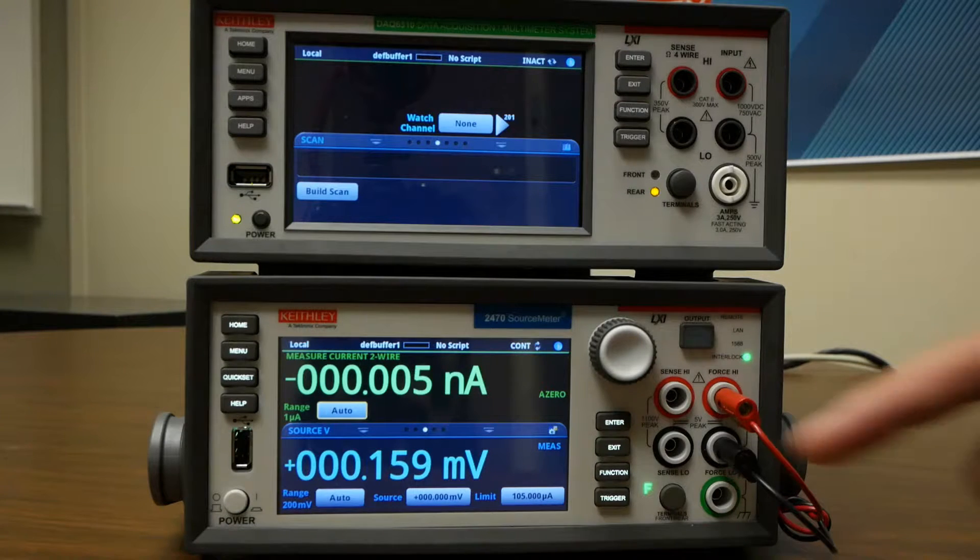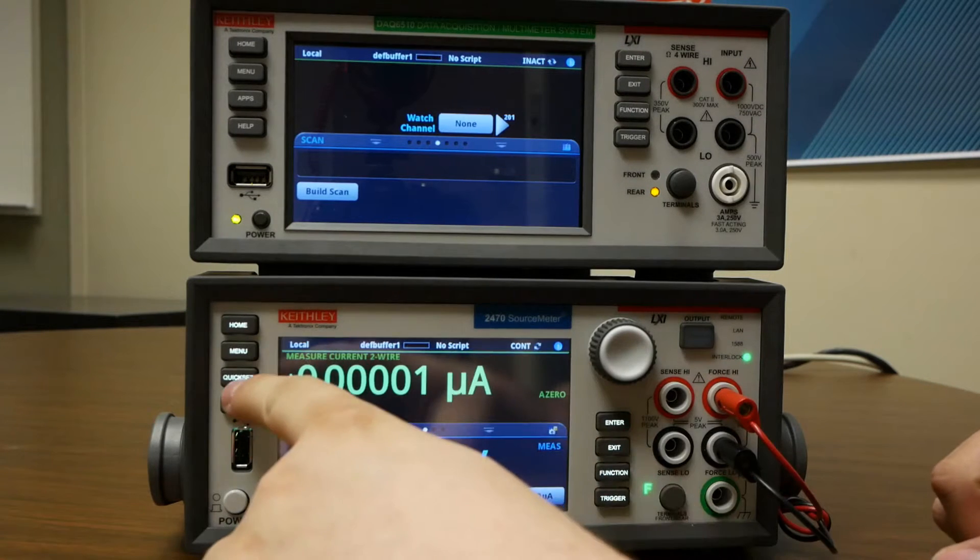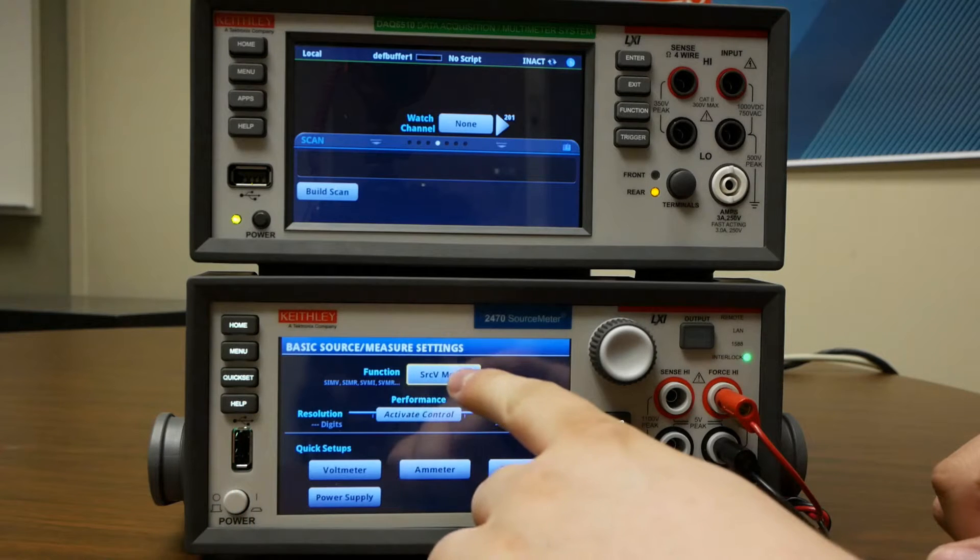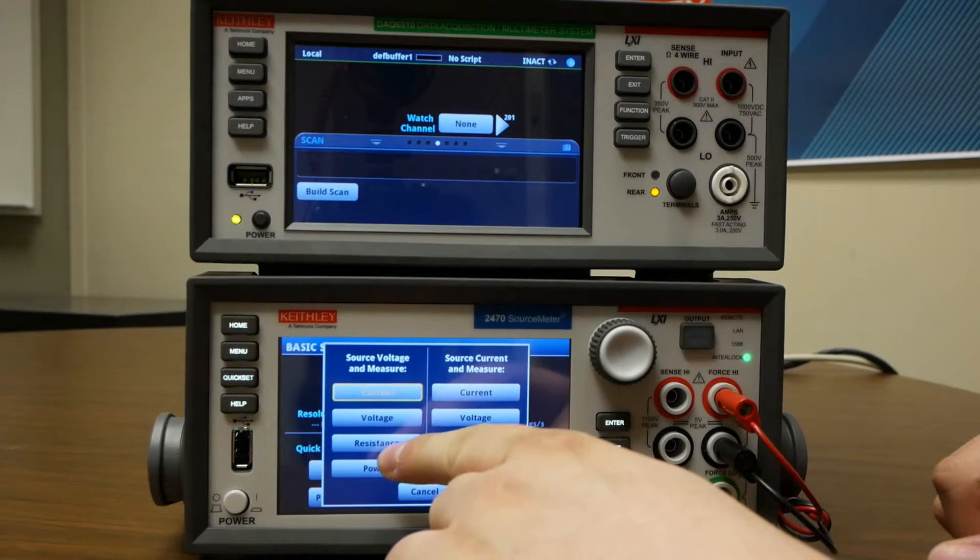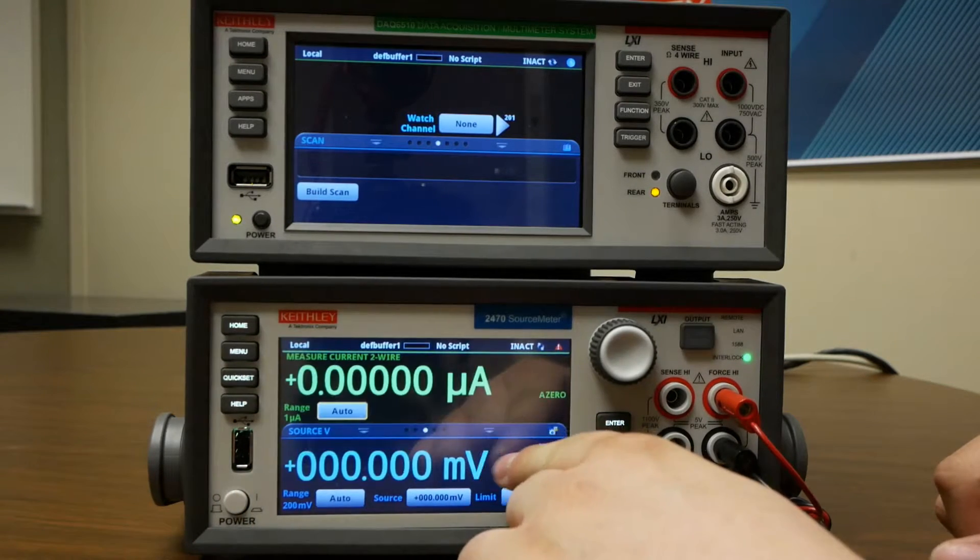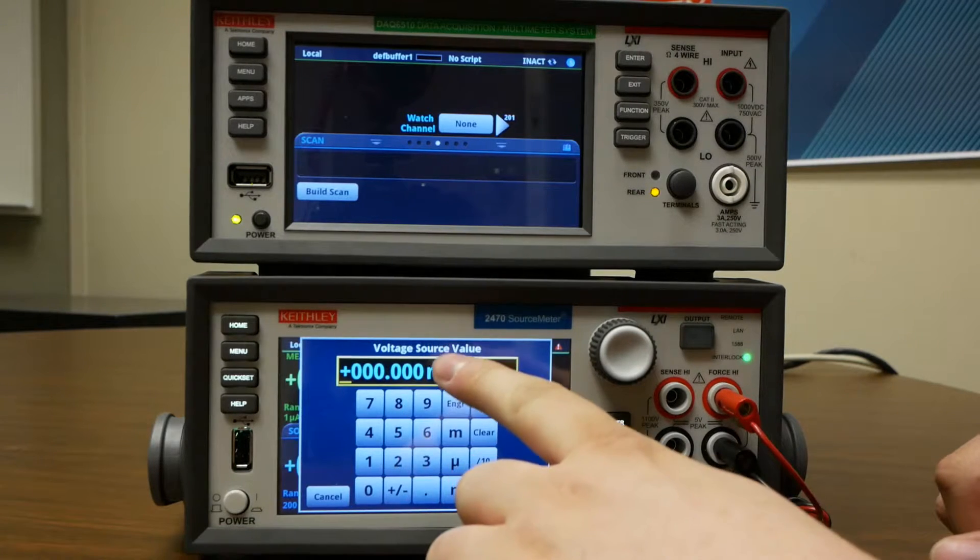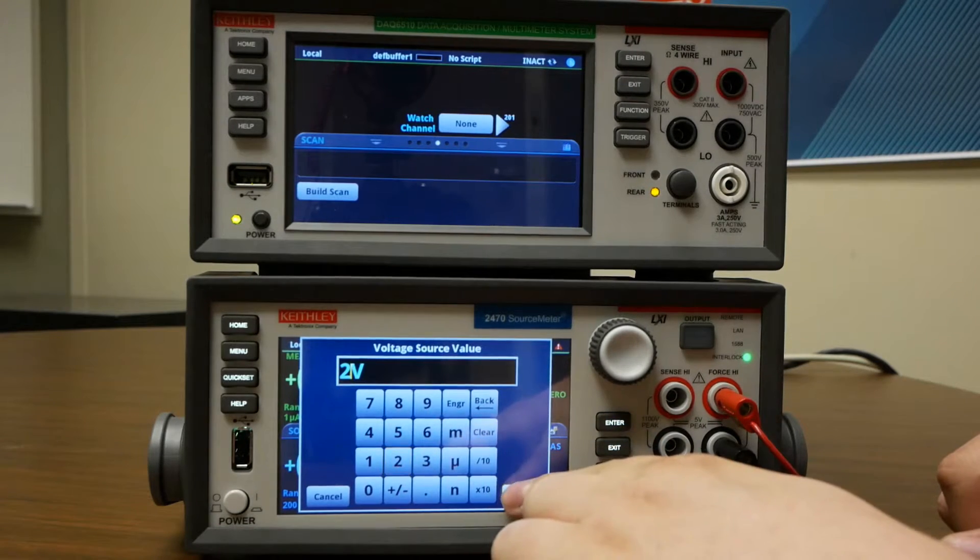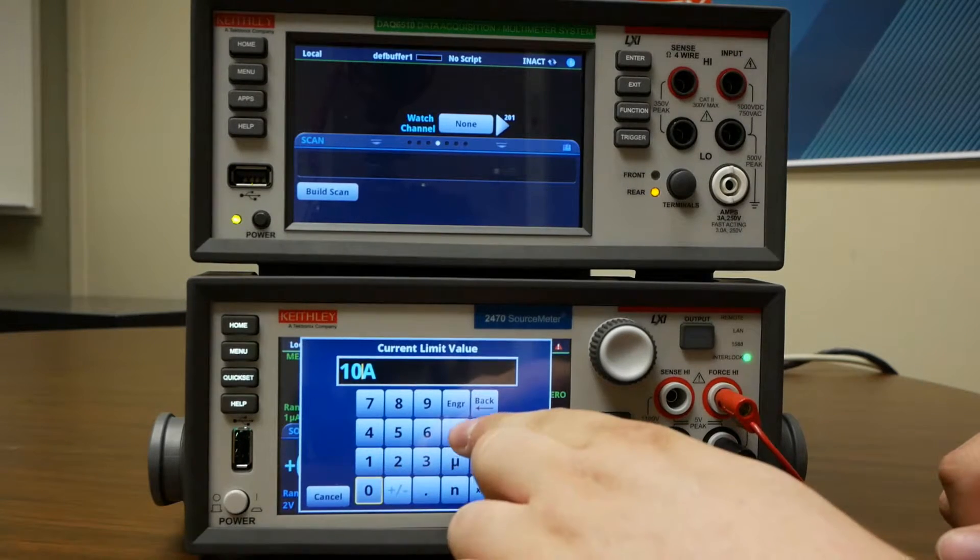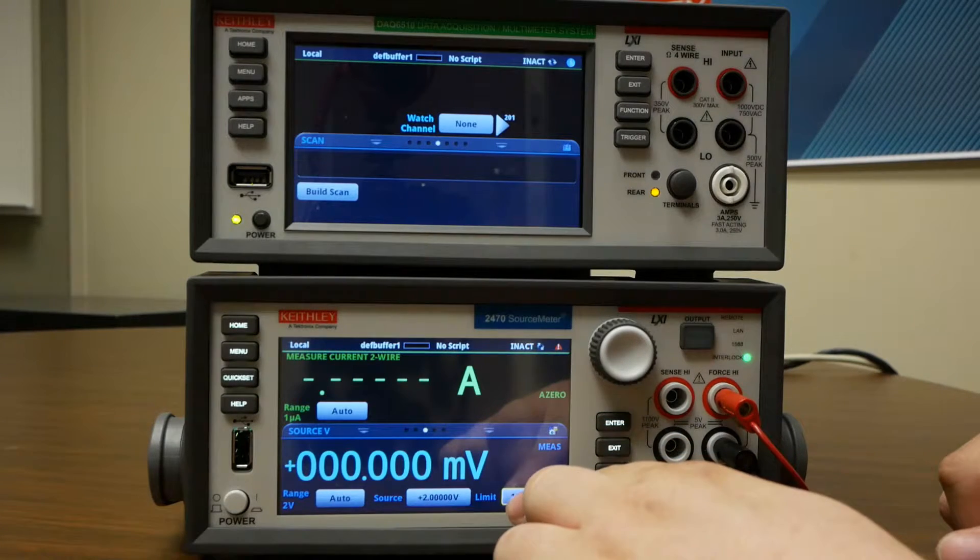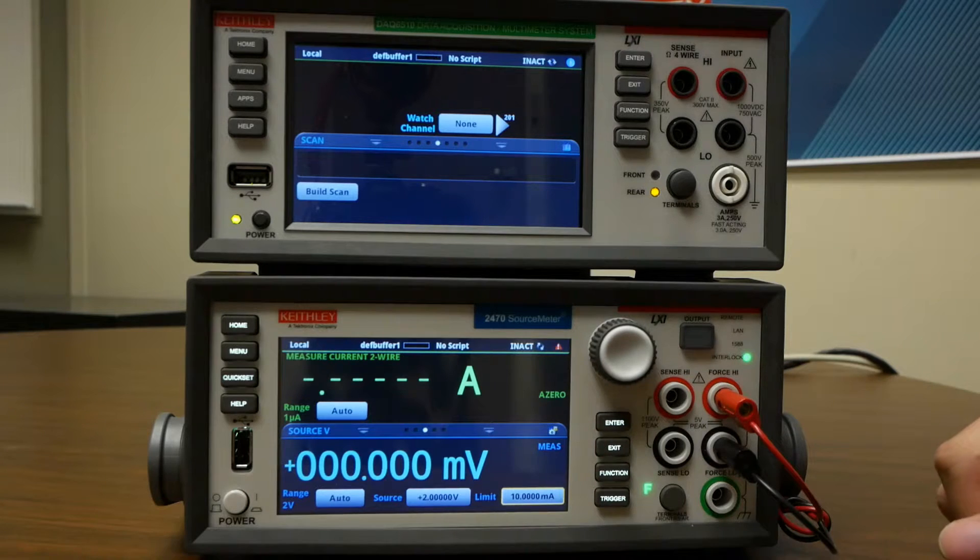Now we'll configure our test. We'll start with the SMU. I'm going to press quick set, change my function to source voltage, measure current. We'll set our source voltage to 2 and set a 10 milliamp compliance current. Now this is all ready to be configured.